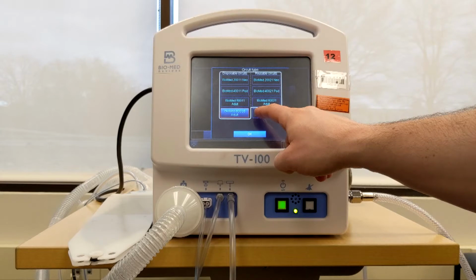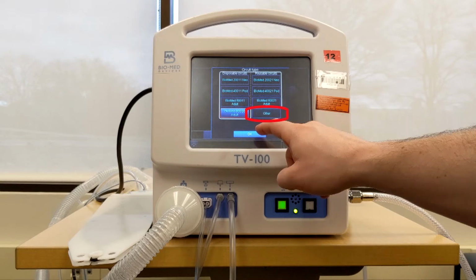The compliance factor of the Bio-Med device circuits will automatically be entered when the circuit is selected, unless we are not using a Bio-Med circuit. Then we need to select Other underneath the reusable circuits. The user should then proceed to the Tools menu and perform a leak test, followed by a compliance test.